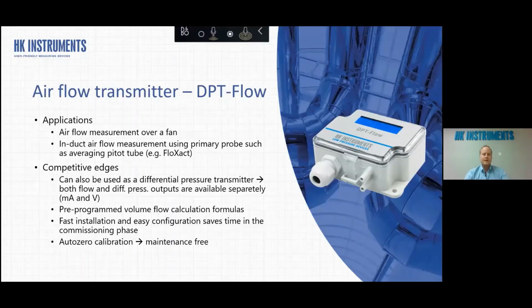Then we have these airflow transmitters. We call it DPT flow. It's like an evolution from the standard differential pressure transmitter. And it can convert the differential pressure directly to the airflow. And you can have the airflow rates directly to your PLC as an analog signal, or also with Modbus. And you can connect it also for in-duct airflow measurements, where you can use, for example, some kind of pitot tube, as we also have our own averaging pitot tube called Floxact.